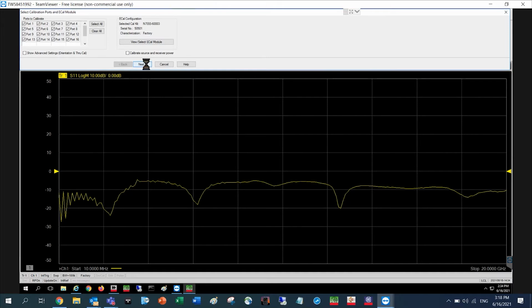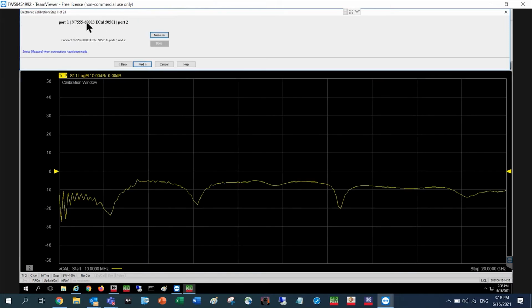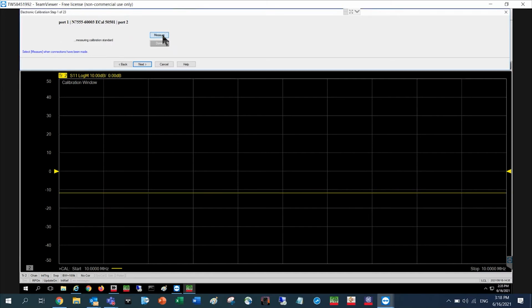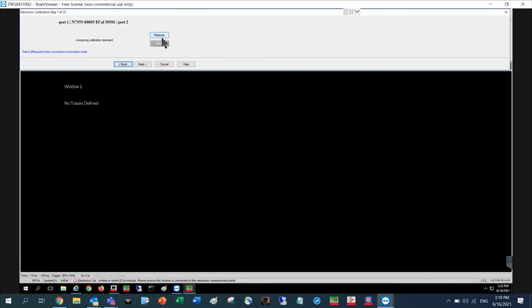We can follow the window prompts. In this prompt, it says to connect port 1 of the VNA to the eCal and connect port 2 of the VNA to the other side of the eCal. Once that is connected, you can hit Measure and the calibration will start. Once the calibration is done, it will prompt you to move over to the next cable. Once everything's completed, you can save the file and use that file whenever needed for the compliance software.